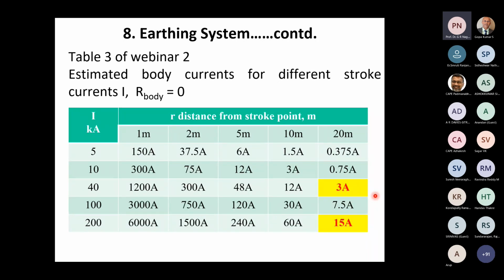Now the currents, body currents, supposing the person has about zero resistance of the body. If you see here again, you'll find that if the radius of the hemisphere is only 1 meter, the currents can be 150 amperes for 5 kiloamperes stroke current. For 40 kiloamperes, that's the mean 50% probability lightning stroke, the step current can be 1200 amperes. If you consider 200 kiloamperes, the body current can be 6000 amperes if we think of this hemisphere of radius 1 meter.